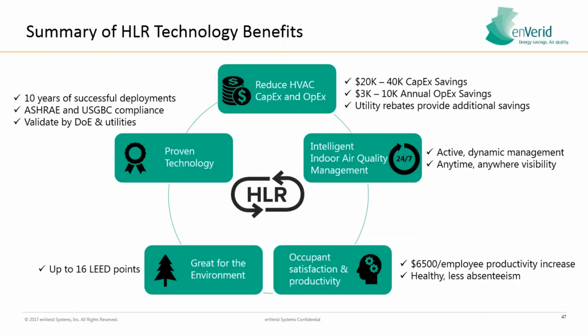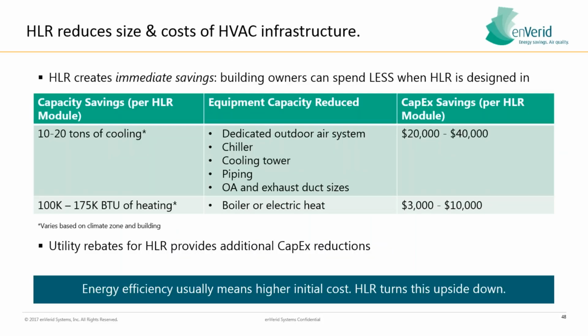So just re-highlighting the benefits: 20 to 40K of CapEx savings per unit is not uncommon. 3 to 10K of annual OpEx savings based on utility rates and net of the service costs as well. 10 to 20 tons of cooling capacity per HLR. You can downsize your DOAS, chiller sizing comes down, ductwork comes down, cooling towers can come down, and then also massive utility rebates in many regions are available as well.